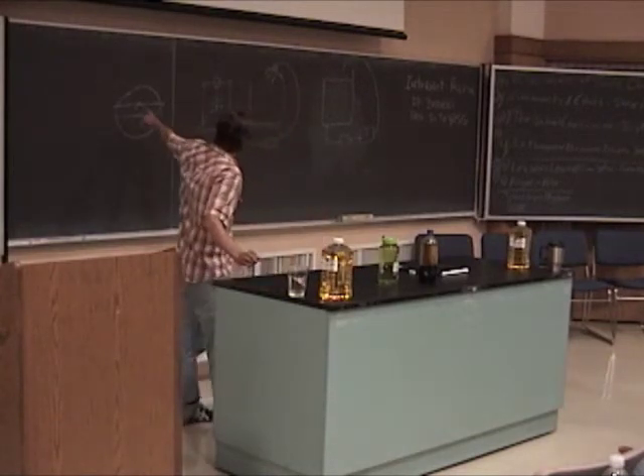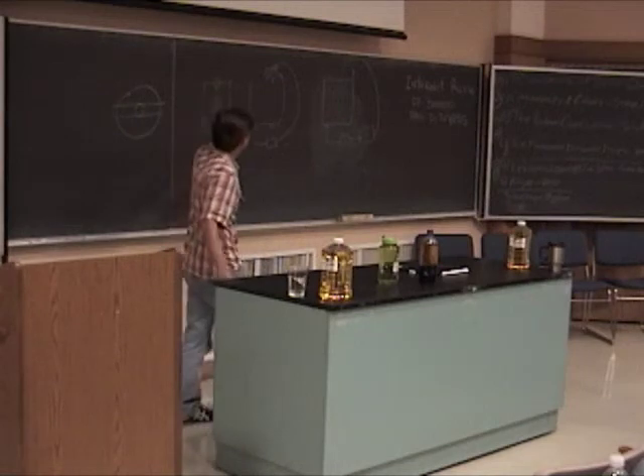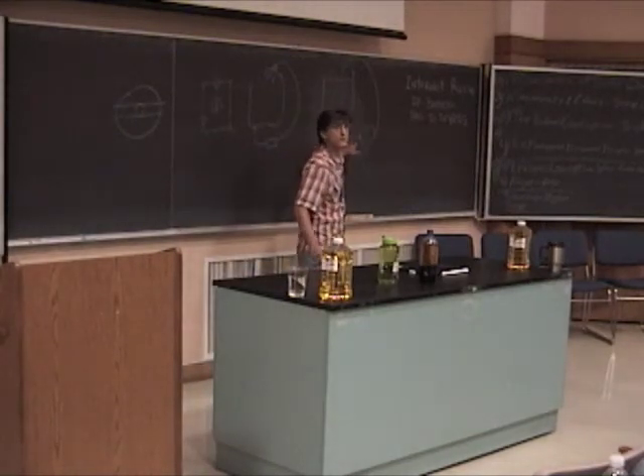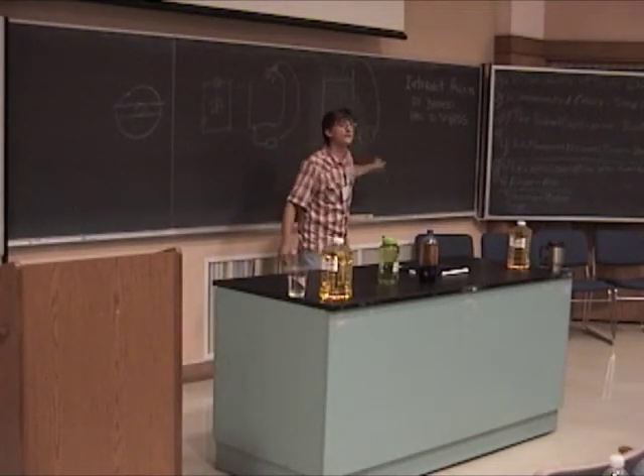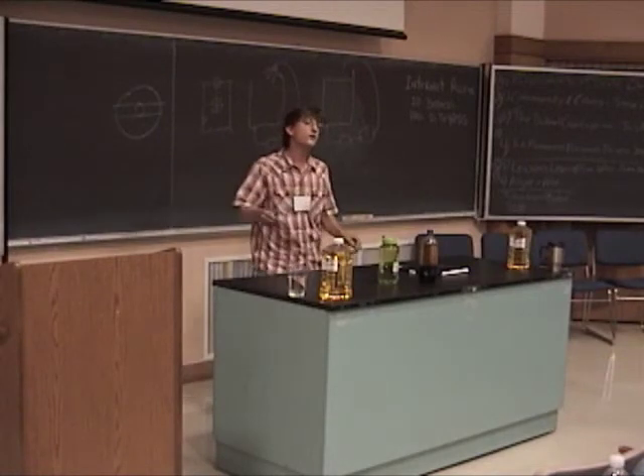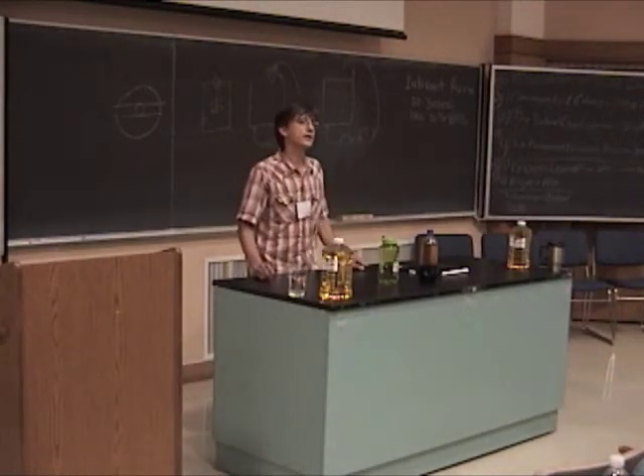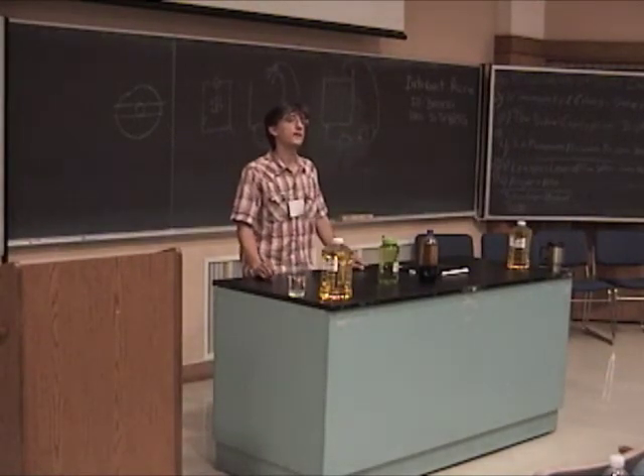I have a regulator on it, and I take it down to between 35 and 40. You mean on the compressed air drive here? No, the centrifuge doesn't run on compressed air, it runs on the pressure of the oil coming out of the pump, hydrostatic opposing jets, between 70 and 120 psi operating range.